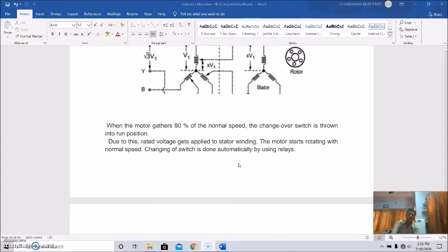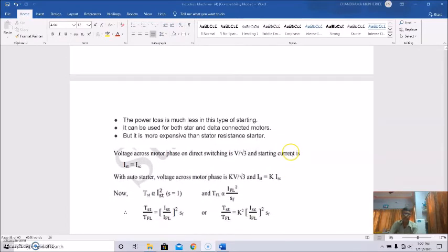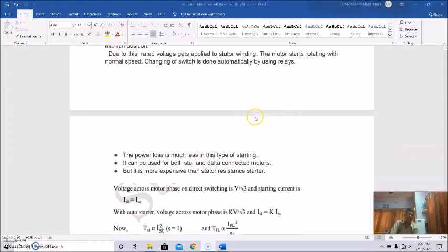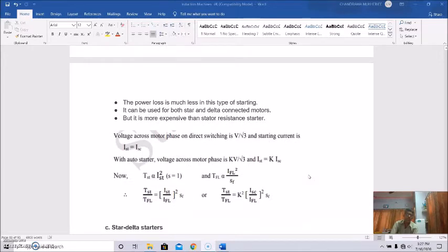So due to this, the rated voltage gets applied to the stator windings, and as a result, the motor starts rotating with normal speed. And changing of the switch is done automatically by using relays. The main objective of this type of starter is that the power loss is much less in this type of starting, whereas in the case of the primary resistance starter, the power loss is very high. So it can be used for both star and delta connected motors, but it is more expensive than the stator resistance starter.